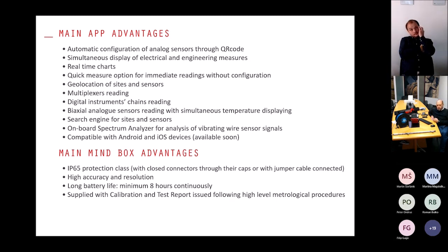You can also, when connecting a vibrating wire sensor, perform a spectrum analysis of the vibration of the sensor. This lets you understand if the sensor is in good or bad health, and if there are noises interfering with the sensor.